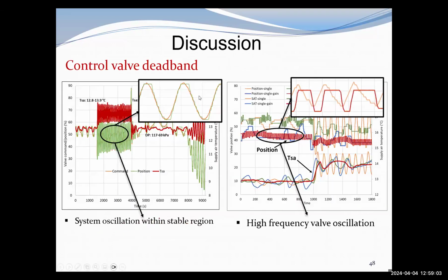We also noted some control valve deadbands based on our test results. That might be the reason for the high frequency valve oscillations. Based on this, maybe in the future we can test it with a better control valve. We also want to test the gain scheduling controller in the pump pipe system.